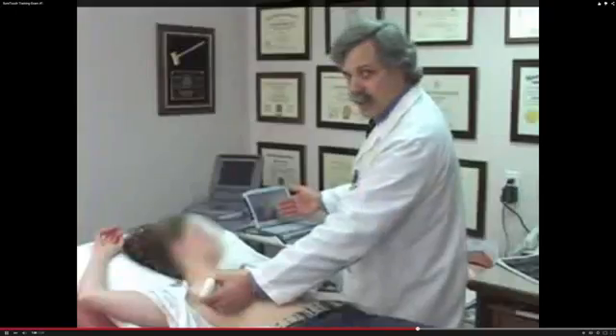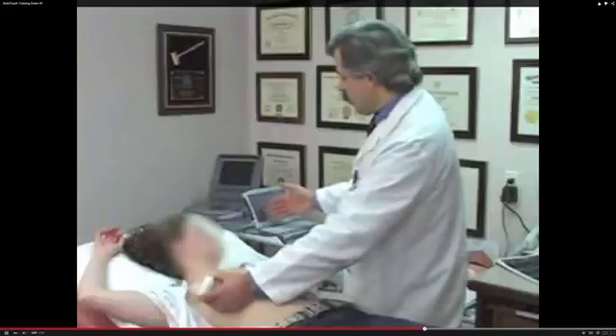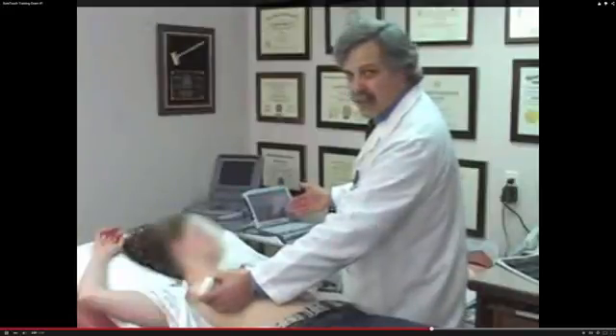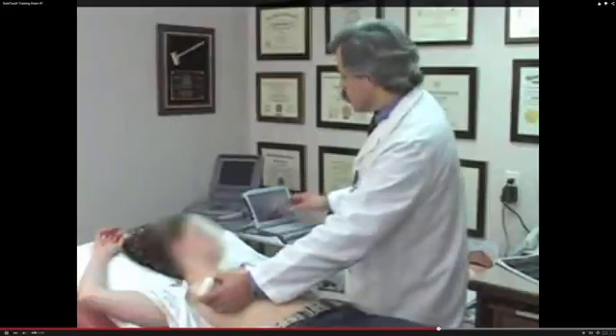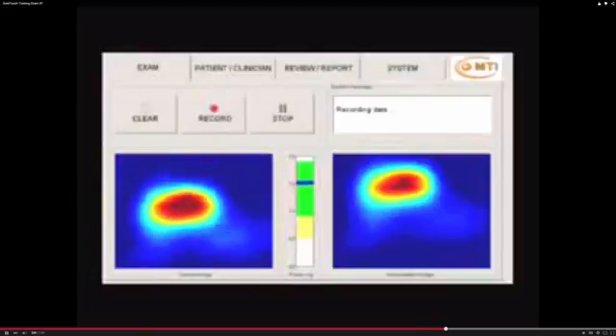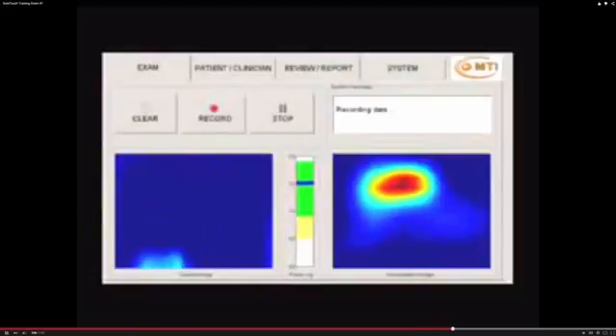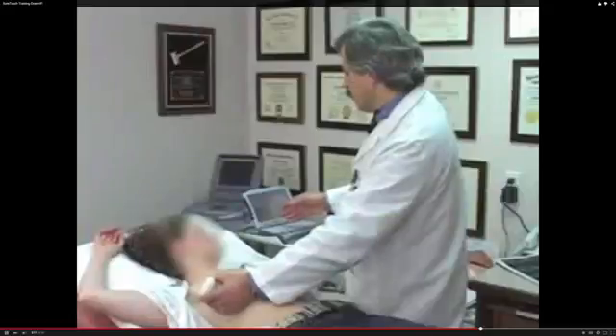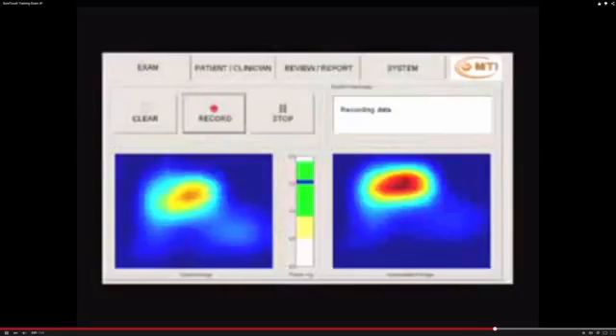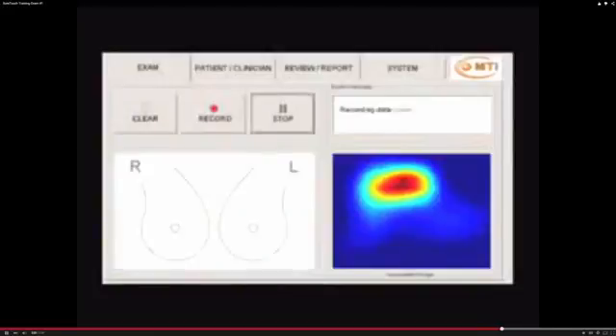If you're in the green area for pressure and you're over the mass, then the accumulated data on the right side of the screen will show a picture of the SureTouch exam of the mass. Note that each data frame consists of all the pressure sensor signals in the two-dimensional array. After you've examined that area for several seconds, 10, maybe 15 seconds, you can press the stop button. This automatically launches a breast map.